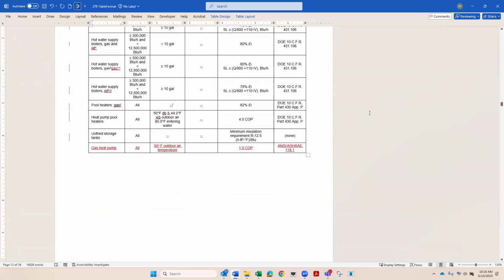Where does the 50-degree outdoor temperature come from? That was what Gary had listed, and that's how they measured it in the standard. Okay, right, never mind - because COP varies by temperature, when you define a COP standard you have to specify the reference outdoor ambient temperature where that COP applies. We could define it at any temperature, like 17 degrees, and you'd have a different COP, but it wouldn't change your metrics. It's just making sure we're referring to the same terminology for the same benchmark for everything.